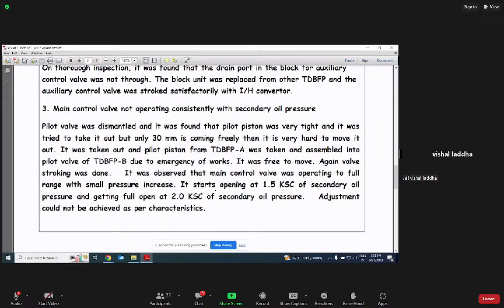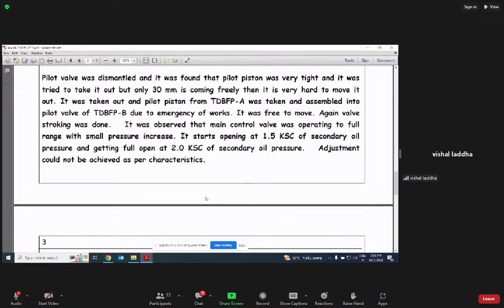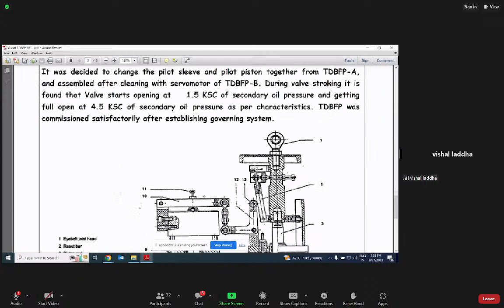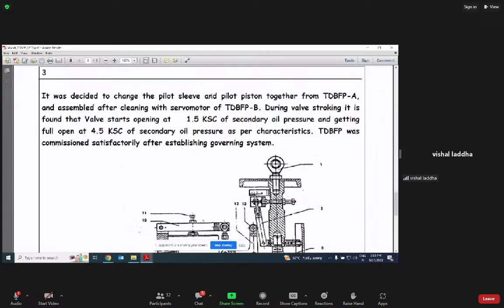Again, valve stroking was done. It was observed that the main control valve was operating to full range with a small pressure increase. It started operating at 1.5 and was fully open at 2 kg. Adjustment could not be achieved as per characteristic. So it was decided to change the pilot sleeve and pilot piston together from TDBFP-A, assembled after cleaning, on the servo motor of TDBFP-B.